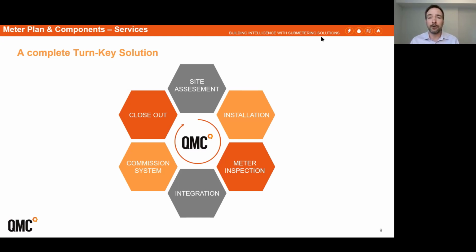Meter inspection is critical. If it's a billing meter, in most applications you need a Measurement Canada approved and accredited service technician to verify the meters were installed properly, since a bill will be completed from that meter system. Even for an energy management system, we still recommend an inspection so that the data coming to an energy manager or a third party for M&V verification is accurate.